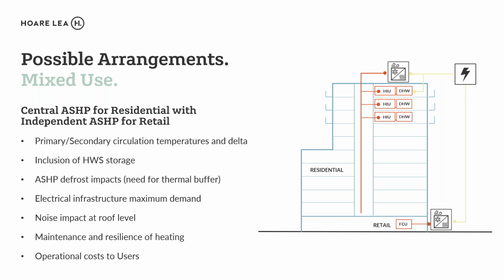We also have impacts of defrost cycles, where that central air source generation needs to have some buffer in there, or multiple units to allow cycling of units to defrost at low ambient temperatures. We obviously have the noise impact, which comes back to central solutions. And then you've got the resilience discussion about how many of those external units you have, as to having units offline or in defrost. And then there's obviously the operational cost because of electric top-up.